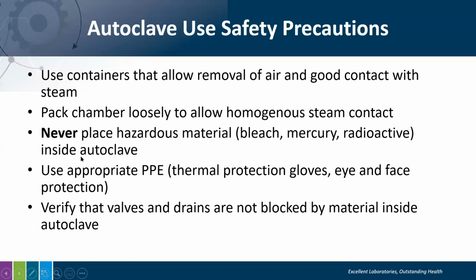People handling the autoclave, the waste, and working on an autoclave need to wear appropriate PPE. That includes thermal protection gloves, eye and face protection, and whatever else is determined by their institution and their risk assessment. And of course, the importance again of maintenance is to verify that valves and drains are not blocked by material inside the autoclave.